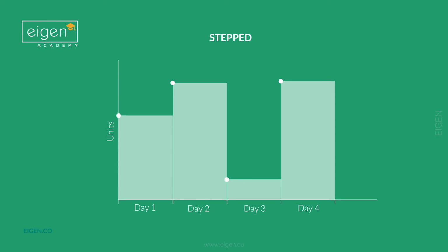But if we were to leave it to the linear interpolation function, we would end up totalizing this, because the linear interpolation will just work out a line between each of the 2 points and draw a straight line and just add up the area under that. So we need to tell the totalize function that the value needs to be stepped and held until you find a new raw value. So that's a use case for the stepped function.